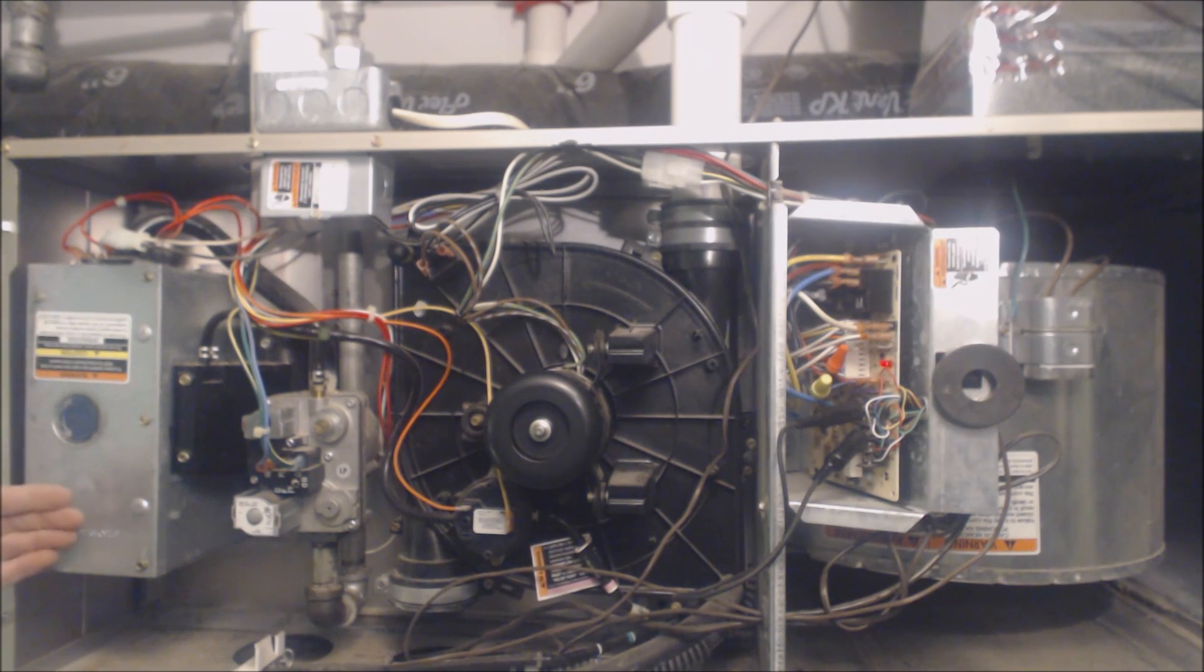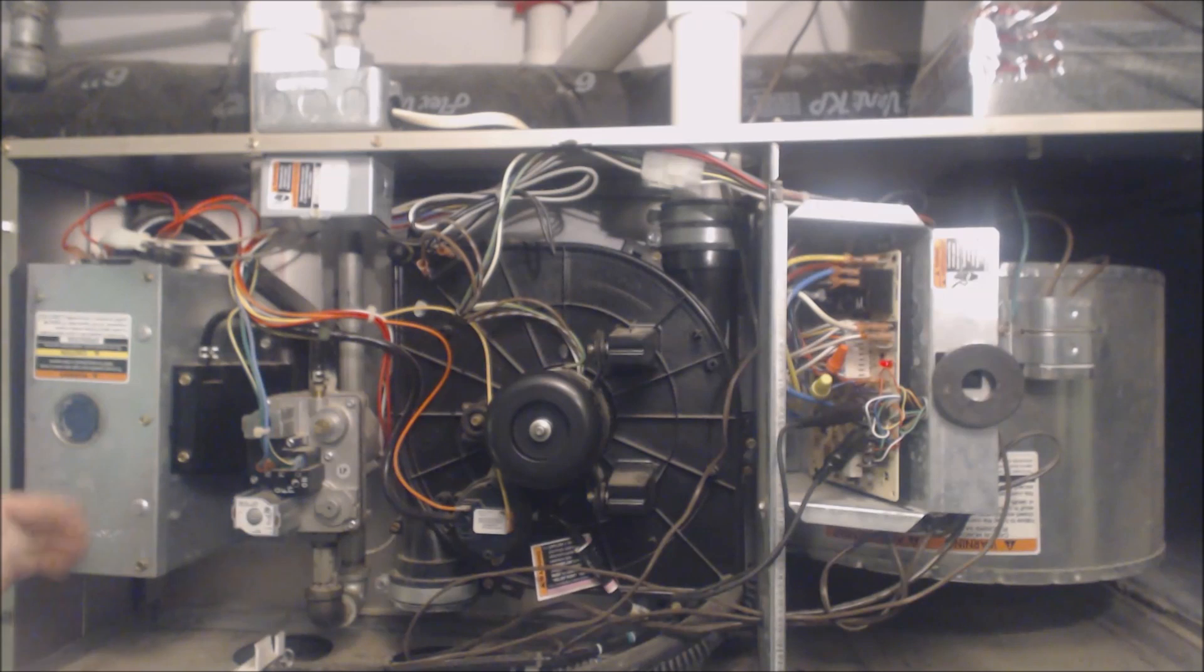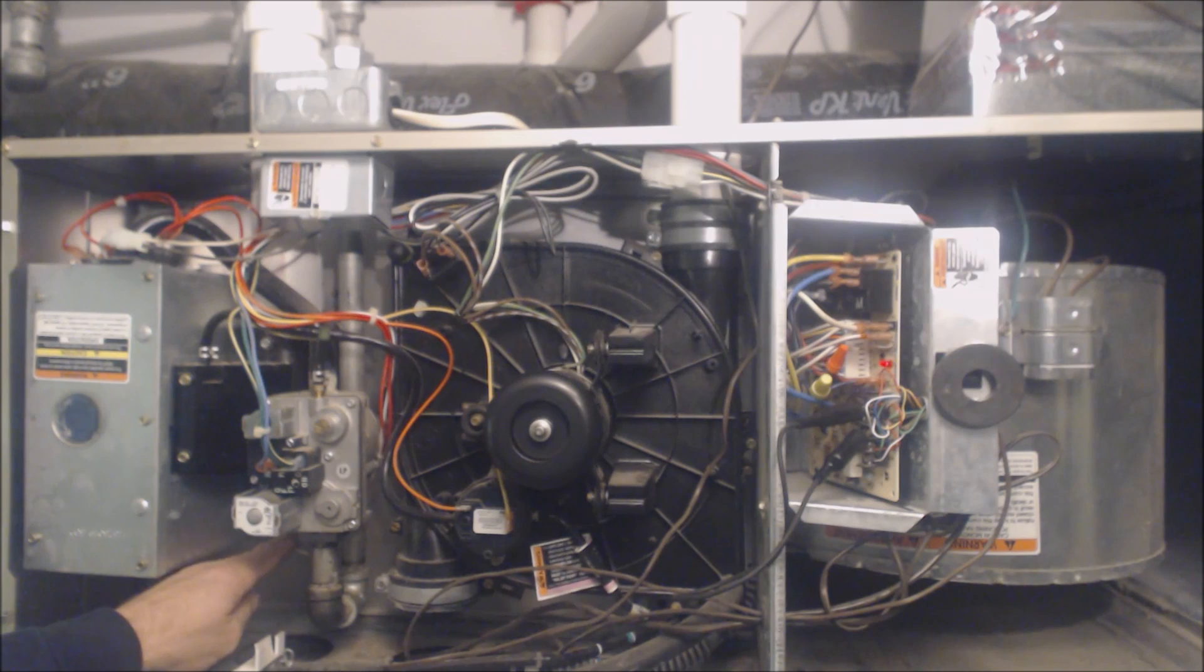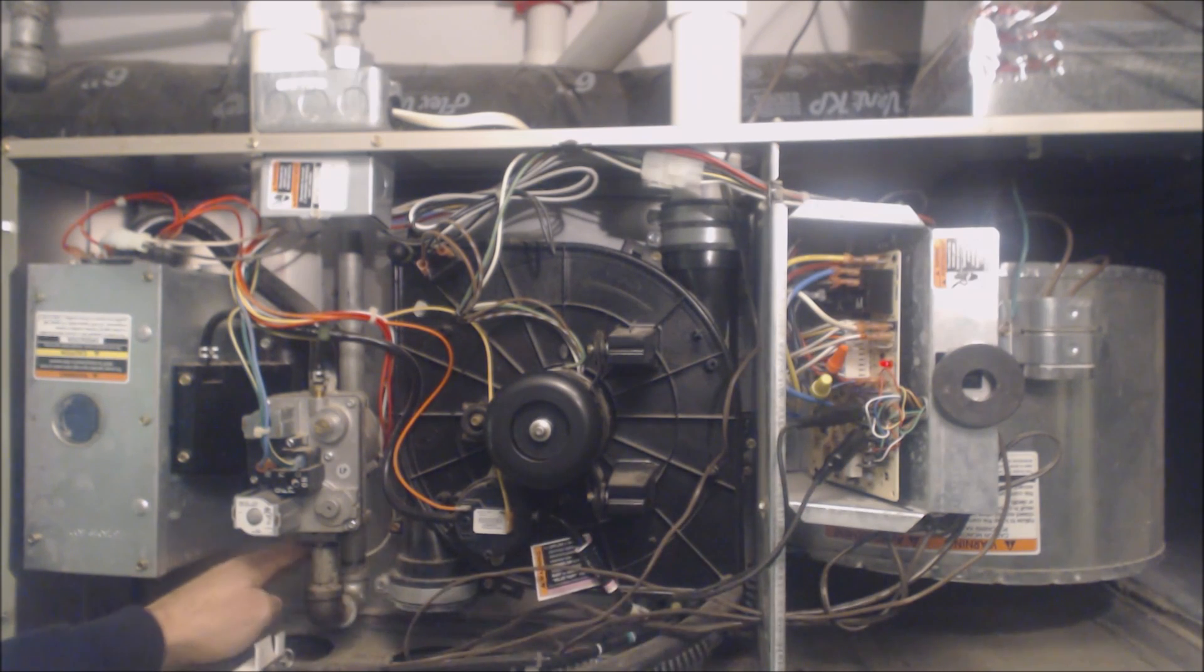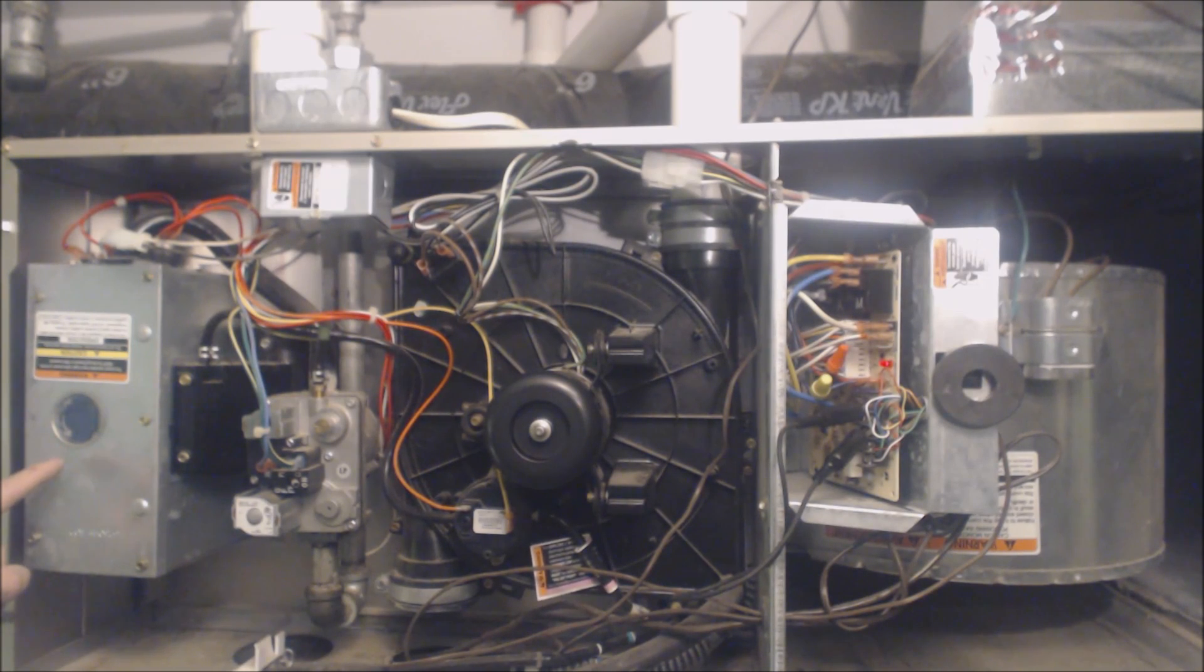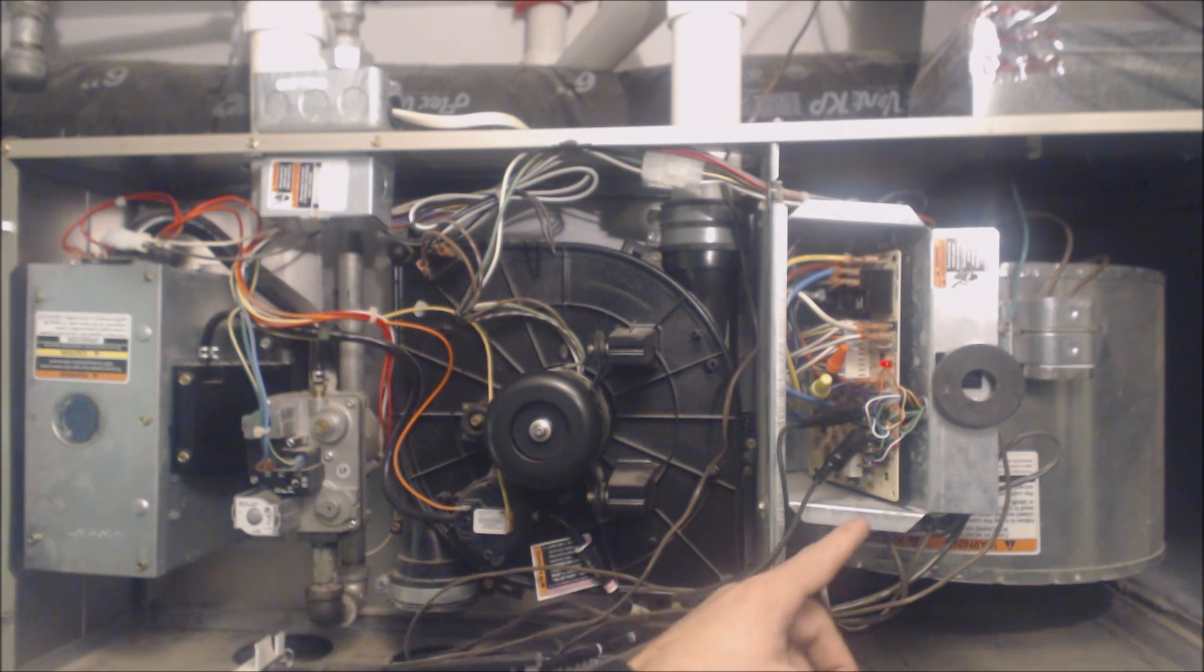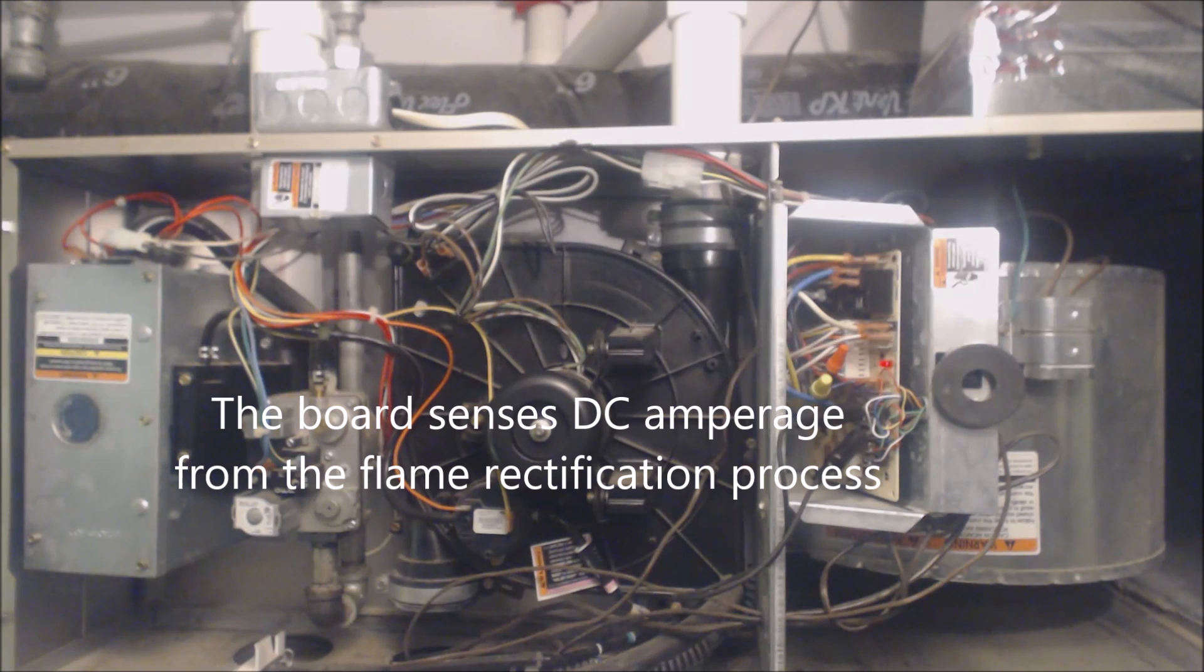It has to travel across all the burners until it comes to the flame rod. On this furnace, the flame rod is actually connected via this white wire back here. The control board sends 90 to 100 volts through the flame rod into the flame. The electricity goes through the flame onto the ground and rectifies it and the board senses DC voltage. After that...